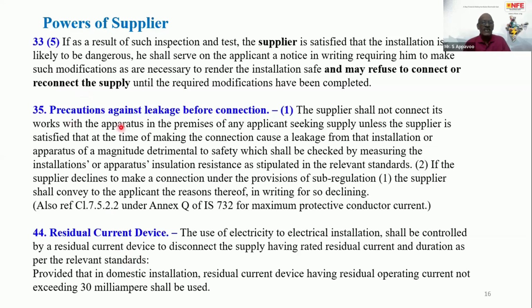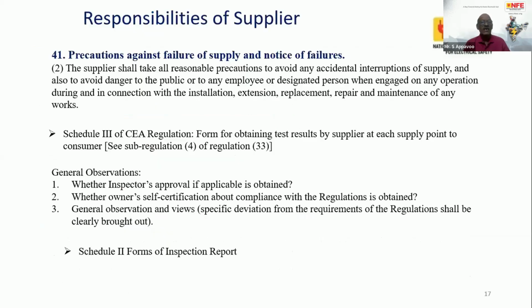Then precautions against leakage before connection also have to be ensured by the supplier. So we can refer to this clause of IS 732, where the maximum protective conductor current is provided. Previously it was not there. From 2019 onwards, there is a clear clause which says what the protective conductor current should be. So suppliers are supposed to go through these clauses to ensure that the installation is not giving much leakage that can harm the occupier.